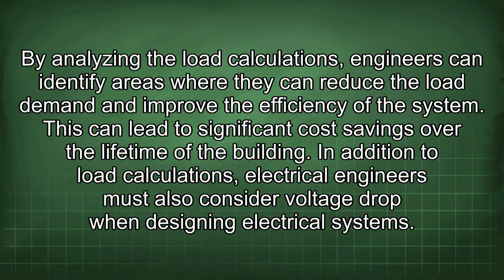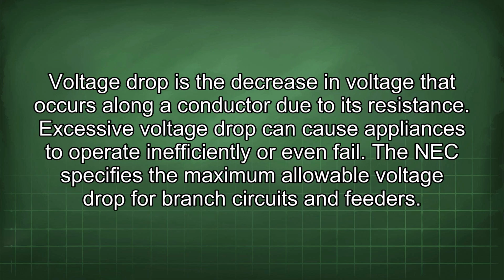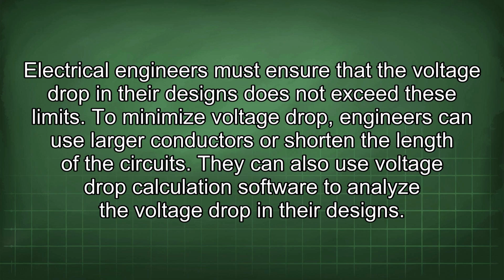In addition to load calculations, electrical engineers must also consider voltage drop when designing electrical systems. Voltage drop is the decrease in voltage that occurs along a conductor due to its resistance. Excessive voltage drop can cause appliances to operate inefficiently or even fail. The NEC specifies the maximum allowable voltage drop for branch circuits and feeders. Electrical engineers must ensure that the voltage drop in their designs does not exceed these limits. To minimize voltage drop, engineers can use larger conductors or shorten the length of the circuits. They can also use voltage drop calculation software to analyze the voltage drop in their designs.